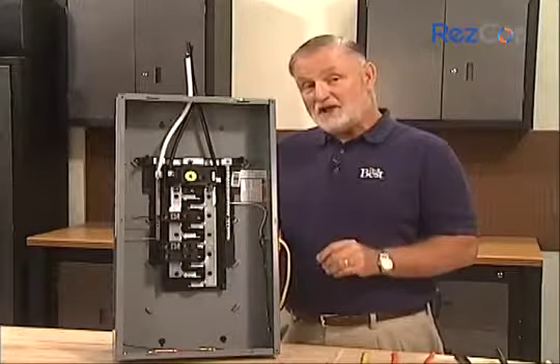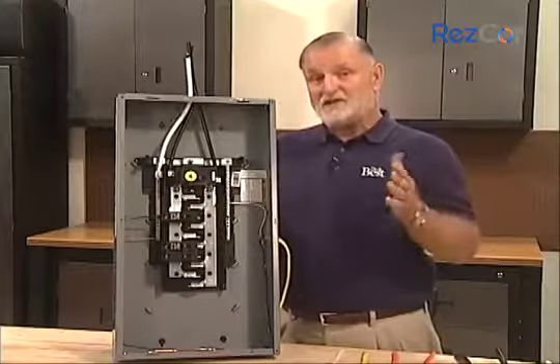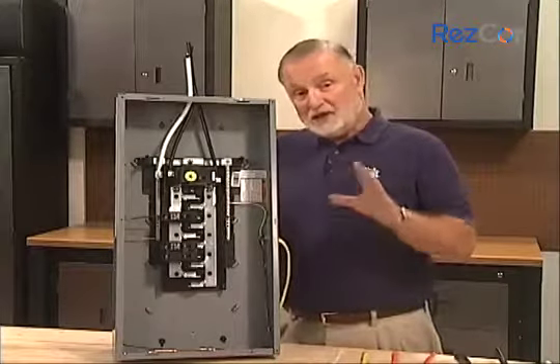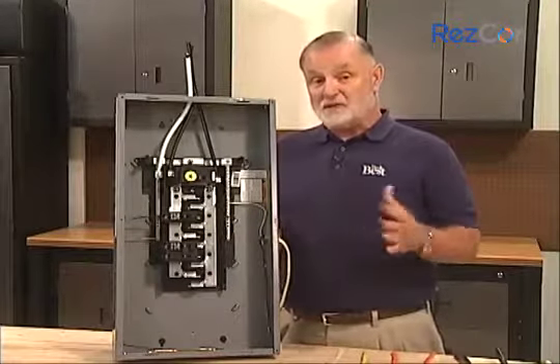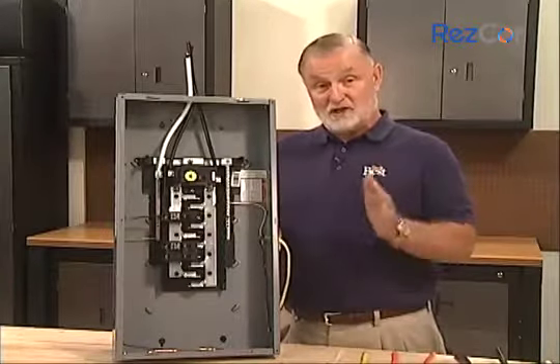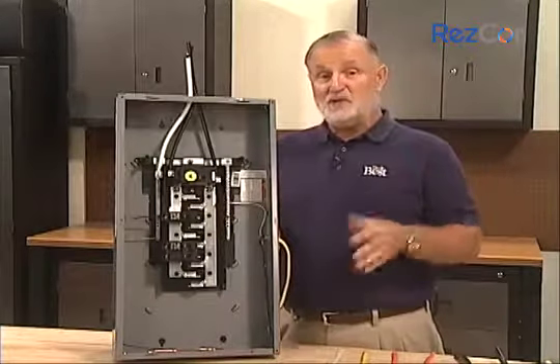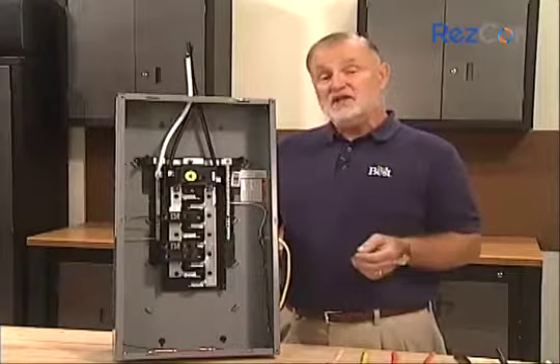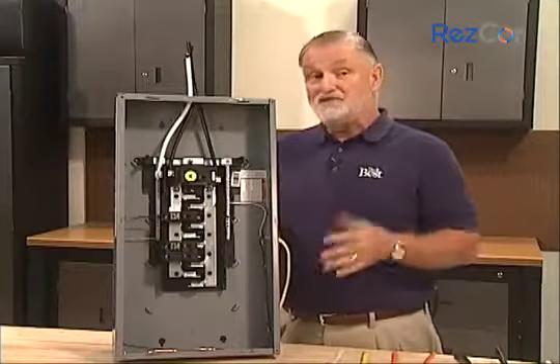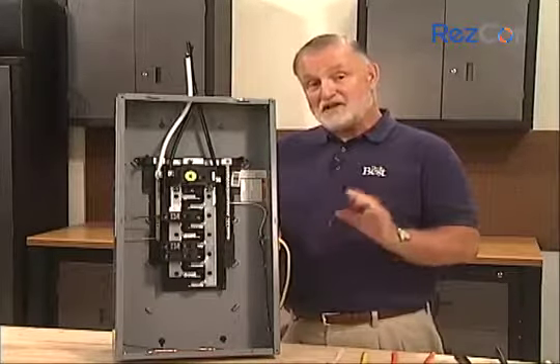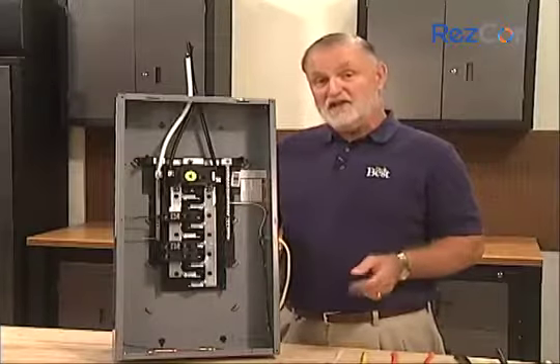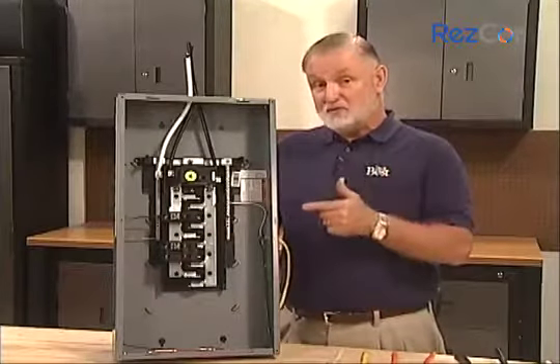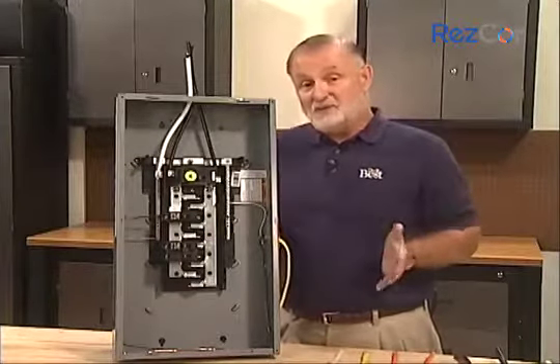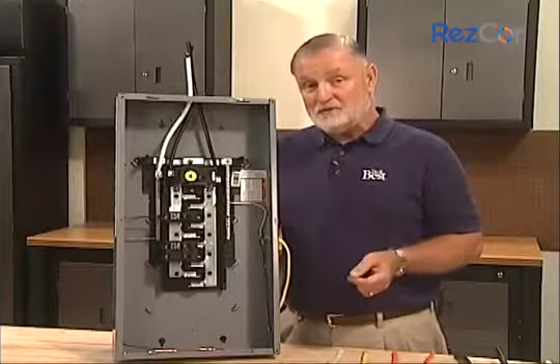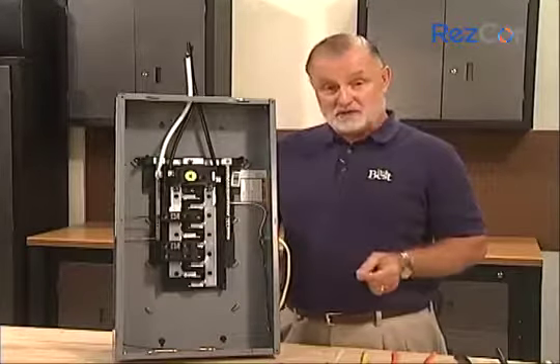If you add another panel off of the main, that panel is called a subpanel. You would add a subpanel if you needed more space for individual circuits in your house. For example, if you had wanted to add another receptacle circuit, but your main panel was completely full. A subpanel is like a main without the main breaker, and it usually mounts next to the main. You don't gain more available power by adding a subpanel, but you do gain more space for circuits.